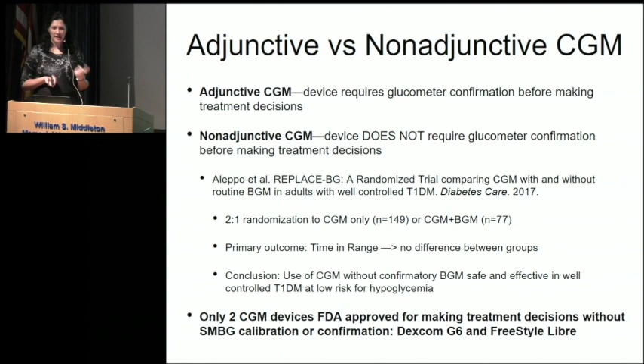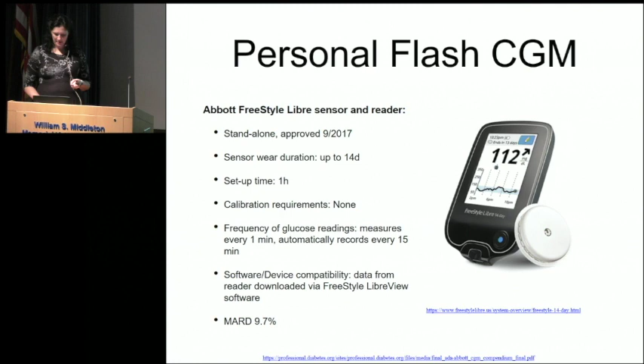So now getting into the personal types of sensors, the Abbott Freestyle Libre is very similar to the professional CGM. This one actually came out in 2017. Patients can wear this one for 14 days. It can only be worn on the back of the arm. The nice thing about this device is that it doesn't require any calibrations. And the personal device has a slightly improved accuracy of 9.7%. But again, this device does not alarm a patient if they're going high or low. It physically requires the patient to wave their reader or phone over the sensor in the arm to get the readings.